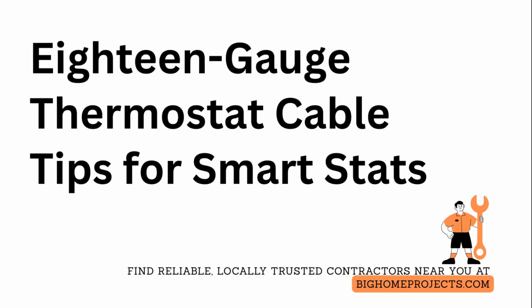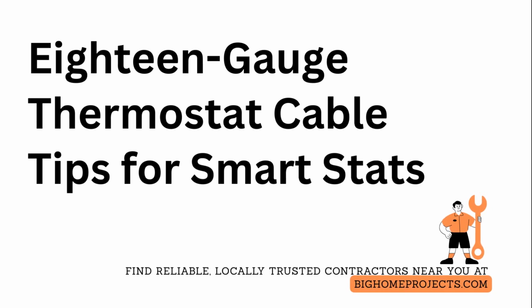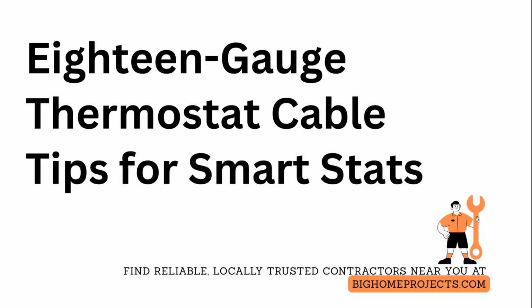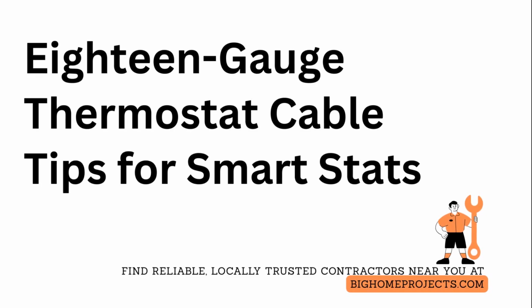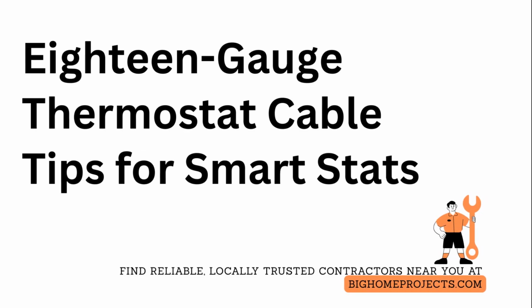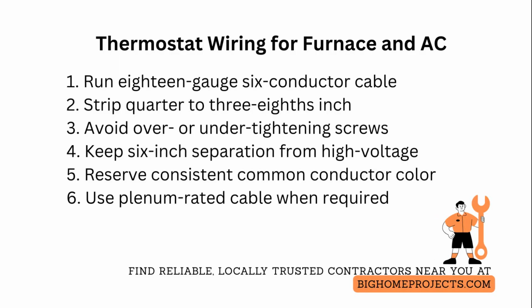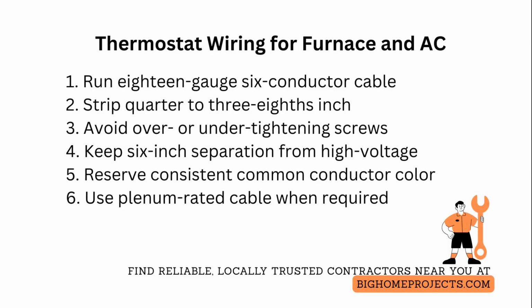Choose an 18-gauge, 6-conductor thermostat cable for furnace and air conditioning combo systems to ensure you have the correct supply run and future-proofing for common controls. When wiring a combined heating and cooling system, run an 18-gauge, 6-conductor thermostat cable from the furnace to the thermostat location and also to the air handler if separate.